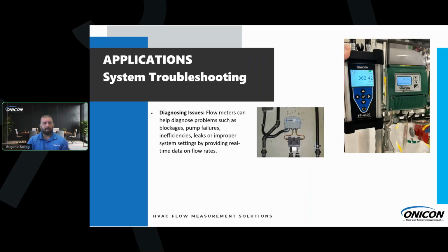Another example for some troubleshooting. This was a recent call from one of our reps. Basically, we have our inline mag. You can see in the picture on the right, the transmitter was reading about 360 GPM. The test and balance came out and thought they should be seeing about double that, around 700 GPM.